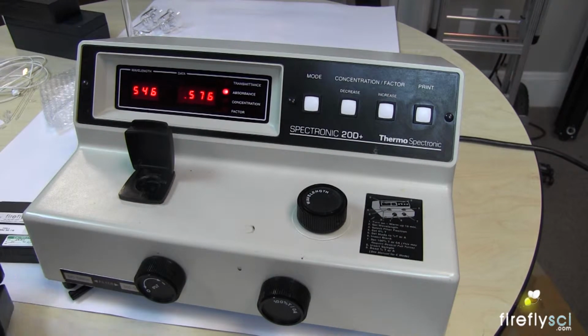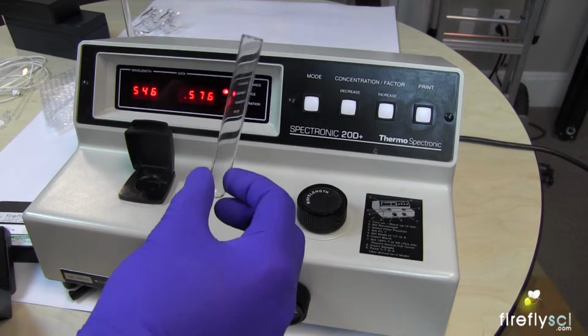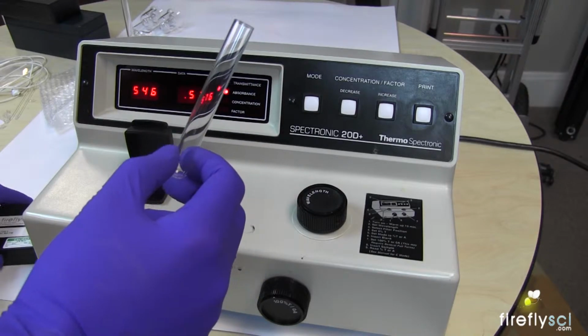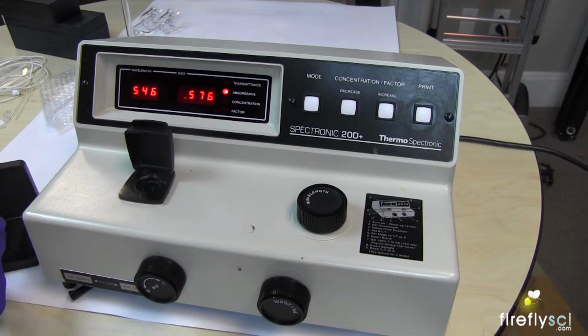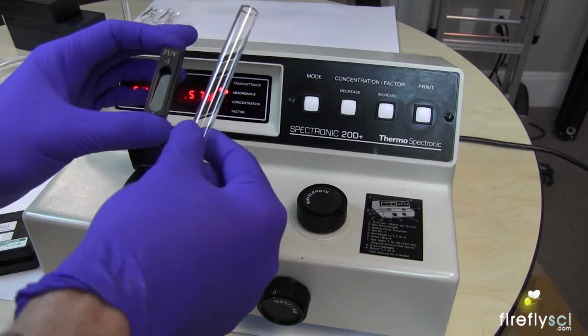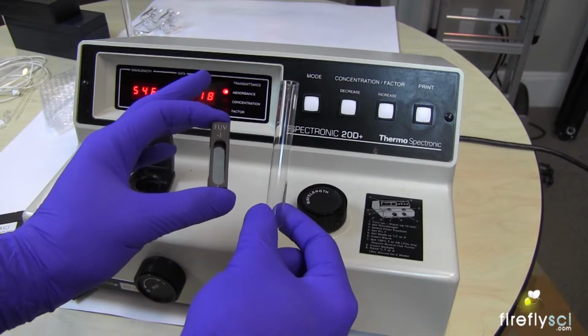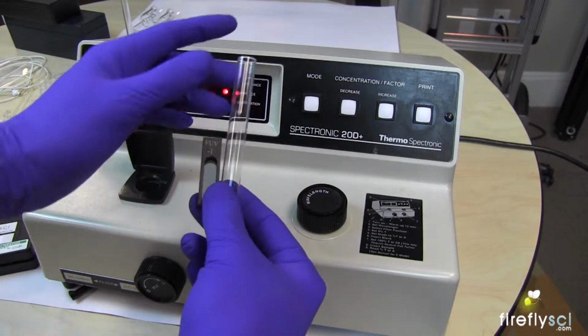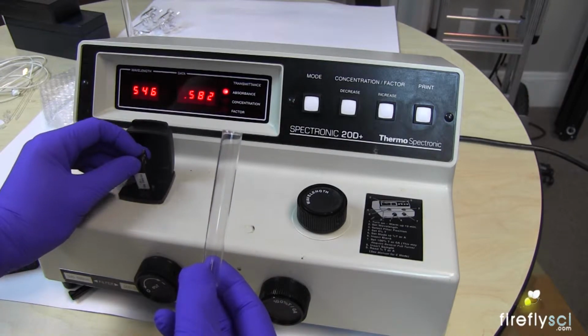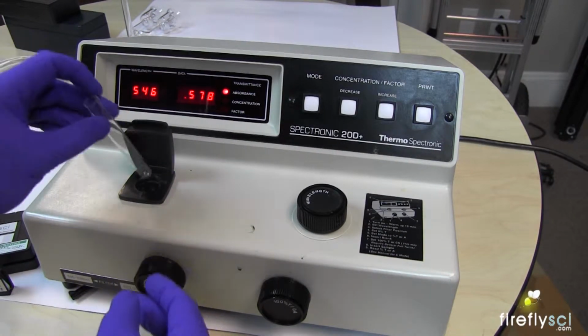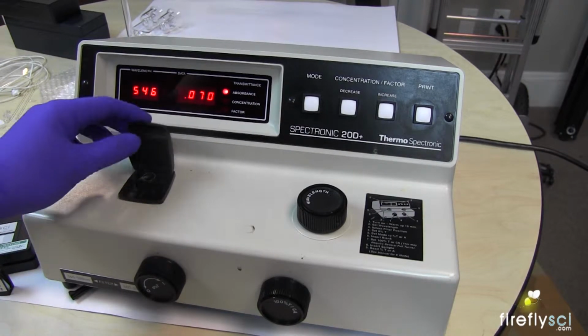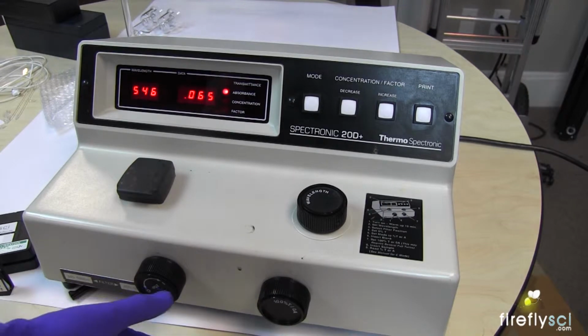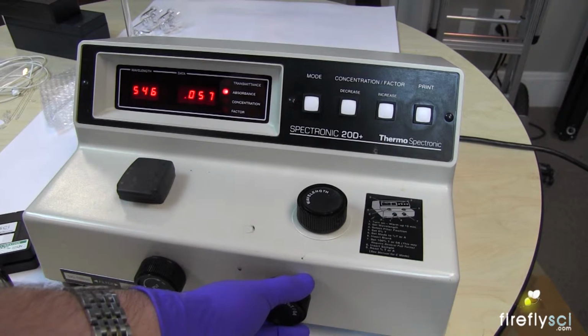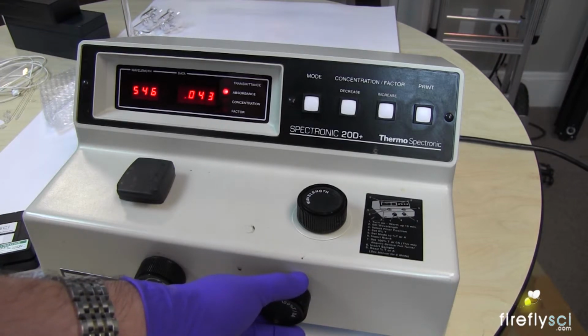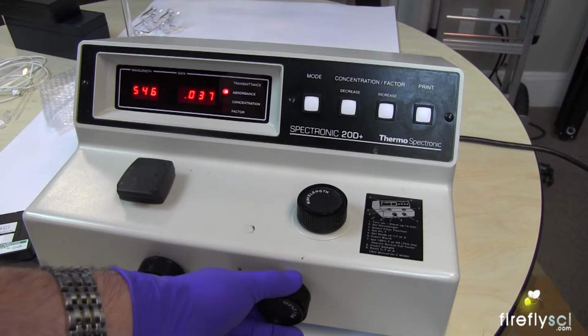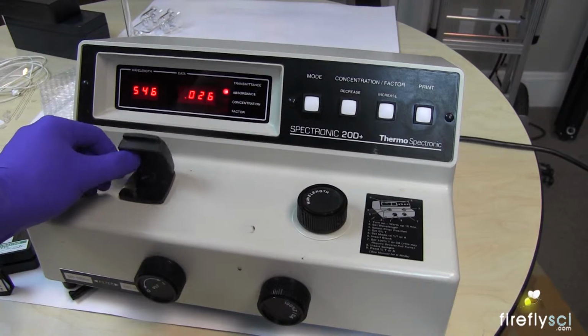Originally I thought you needed these big, huge test tubes that go in these machines to blank it. Let me show you a comparison in size between a standard cuvette and this test tube. You can see this test tube is huge compared to the cuvette. Originally I put the cuvette in this machine and it fell all the way to the bottom. But when you put the test tube in, it fits really nicely, the cover just closes, and then you can blank the machine. I mean, you can zero the machine. Now the problem is we blank our calibration standards with air. We don't use any kind of glassware in there.